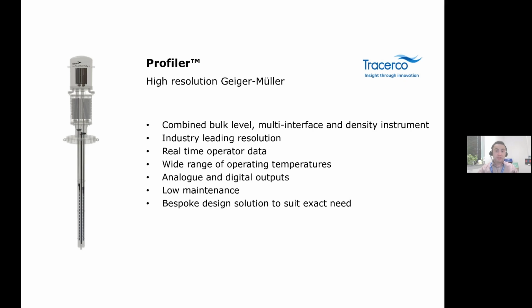Typically, each source is directed using a collimating rod into two detectors above and below the plane of the source. This collimation reduces the number of low-energy gamma sources used and stops radiation in all directions except that towards the detector. This creates a continuous measurement range by directing each radiation beam up or down. Measuring density change in this way allows for the most efficient operating condition to be maintained, as well as monitoring effectiveness of chemical additives and mud washing regimes.